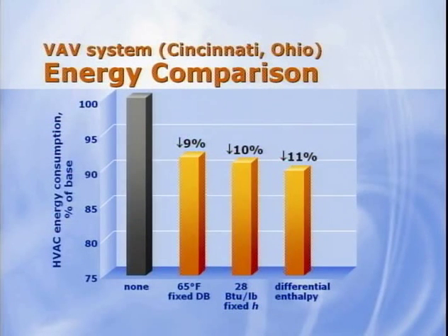For example, we use Trace 700 to analyze an office building located in Cincinnati, Ohio. ASHRAE 90.1 2004 does not require an economizer for this location. In this example, the differential enthalpy economizer resulted in the most energy savings, about 11% compared to a system with no economizer. Although for this particular building and climate, the other, less expensive methods did nearly as well. Of course, climate, building usage, and utility costs impact the operating cost differences of these economizer control methods.